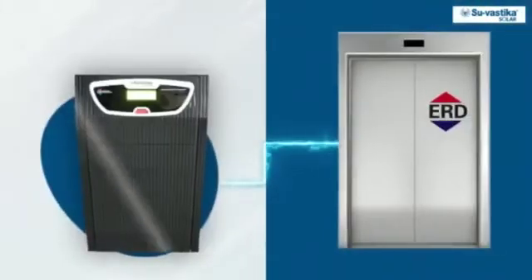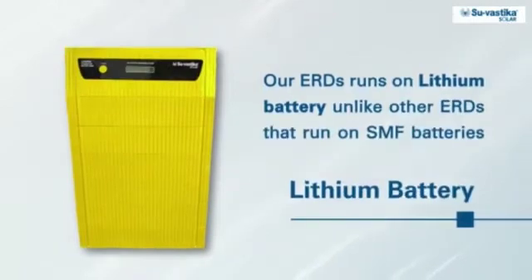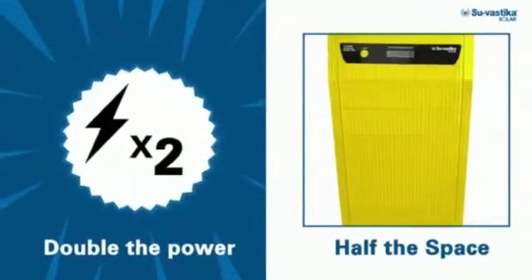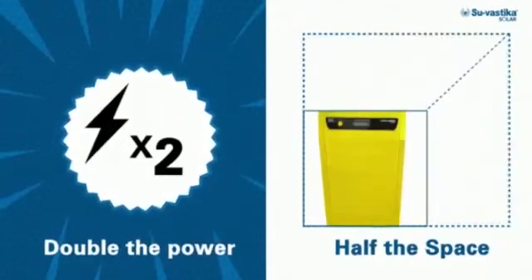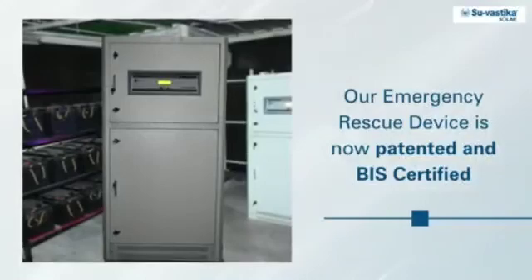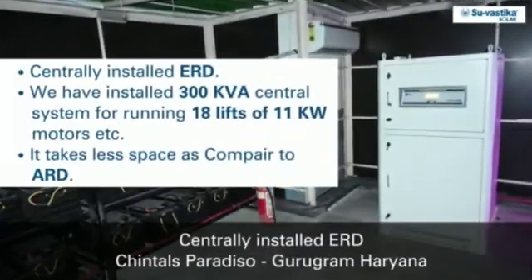ERD has the capacity to run about 12 lifts simultaneously for up to 10 hours. It is cost and space friendly. Our ERD runs on lithium batteries, unlike other ERDs that run on SMF batteries. Lithium batteries last up to two times longer than SMF batteries while also saving space within the unit. Our Emergency Rescue Device is now patented and BIS certified. Glimpses from Chintals Paradiso project — we installed our ERD here.